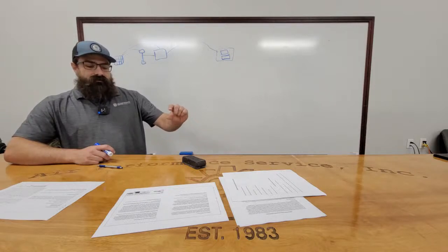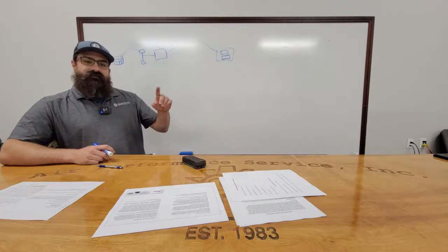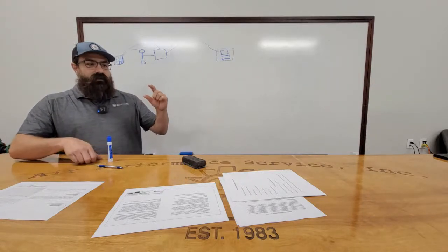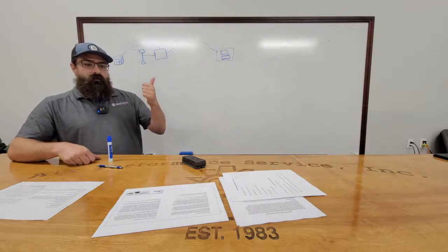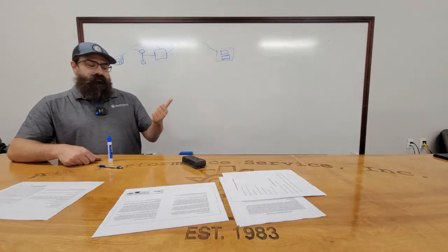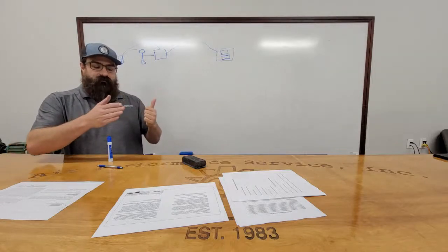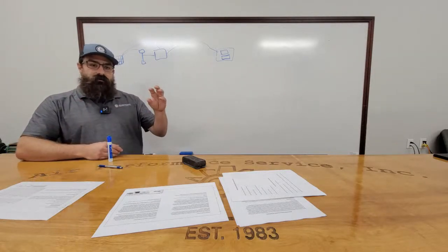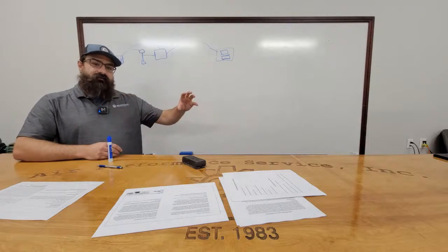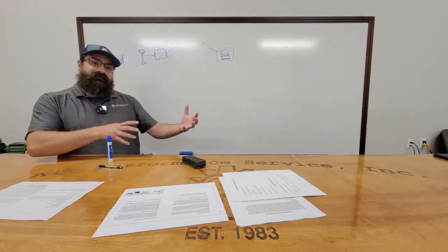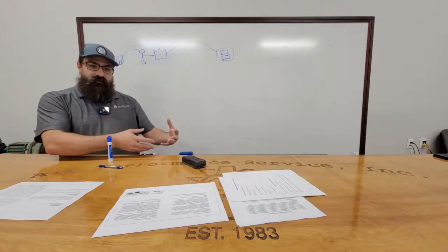a certain percentage. So each VAV box gives us a demand, right? It's called terminal load, which is deviation from set point, basically. The further away you are from set point, the higher your terminal load is going to be. So we can look at terminal load and bring those in and calculate it based on that. Or we can just look at pure space temperature and do an average and bring them on that way.